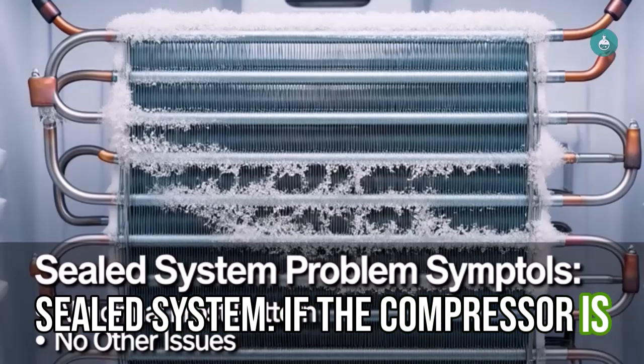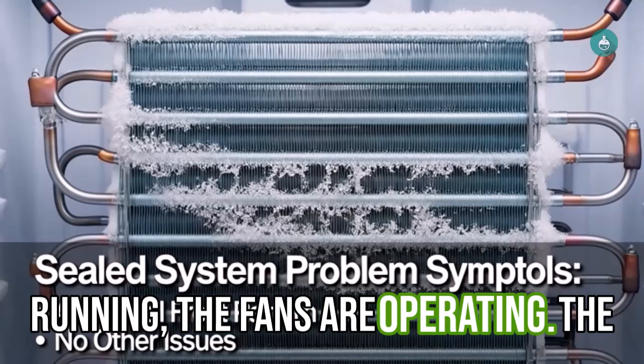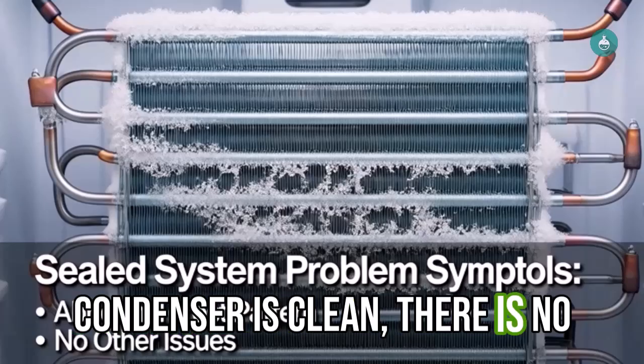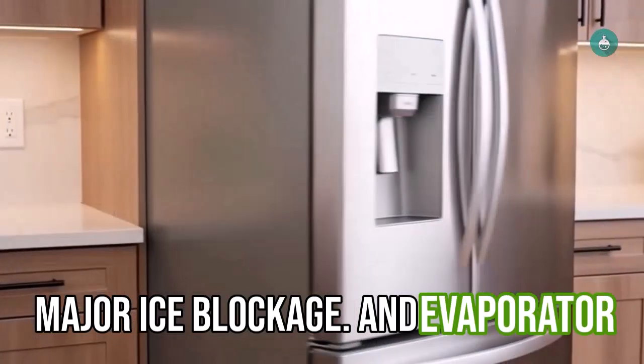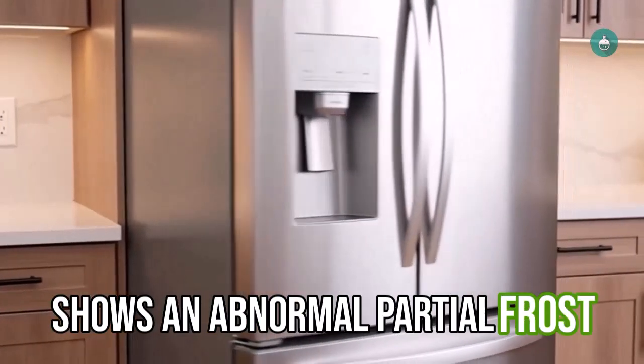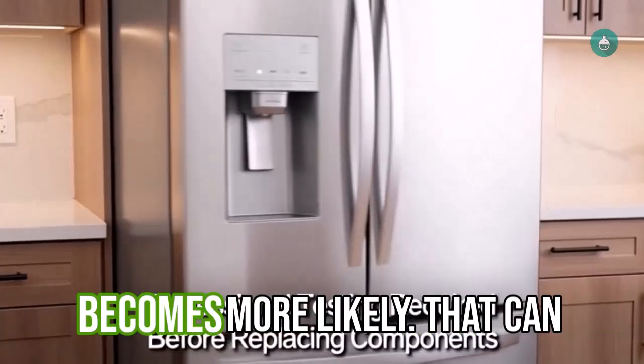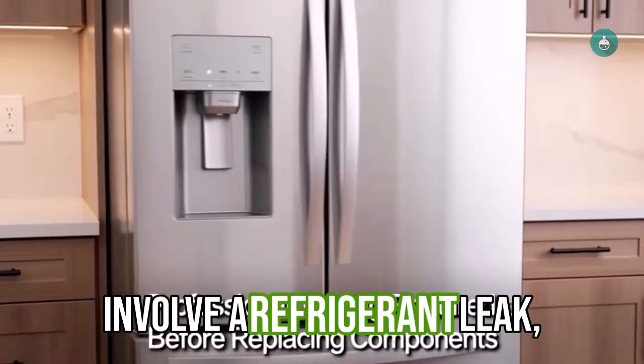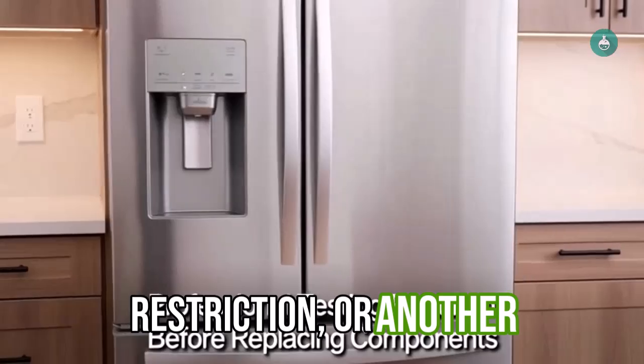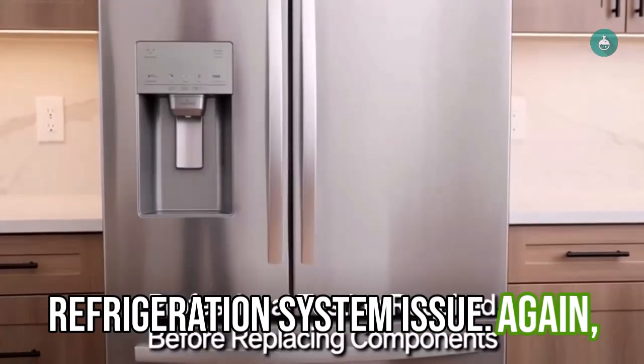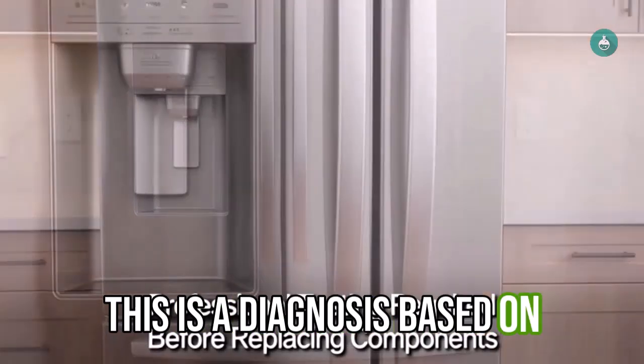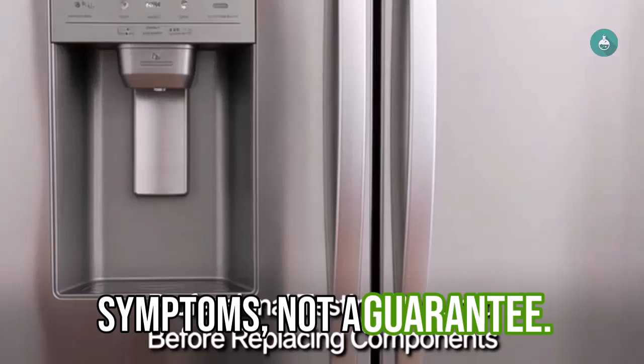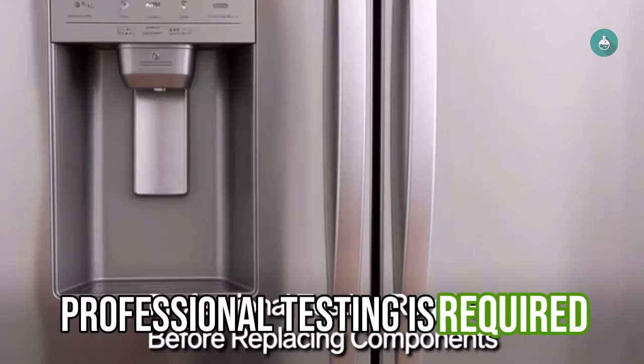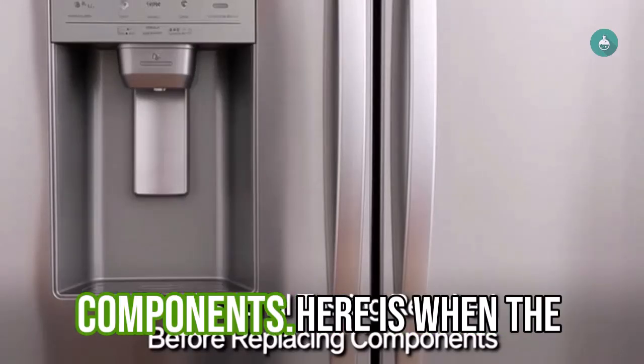If the compressor is running, the fans are operating, the condenser is clean, there is no major ice blockage, and the evaporator shows an abnormal partial frost pattern, a sealed system problem becomes more likely. That could involve a refrigerant leak, restriction, or another refrigeration system issue. Again, this is a diagnosis based on symptoms, not a guarantee. Professional testing is required before replacing expensive components.